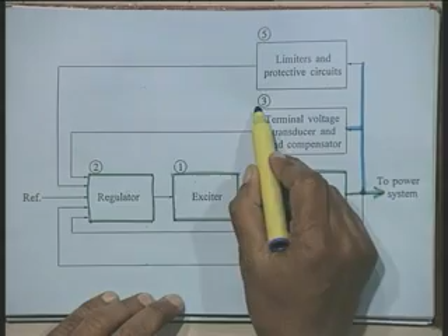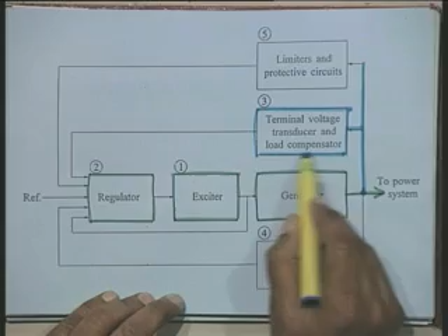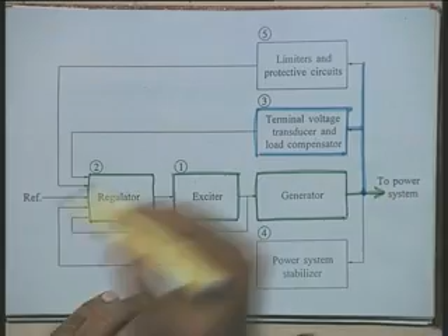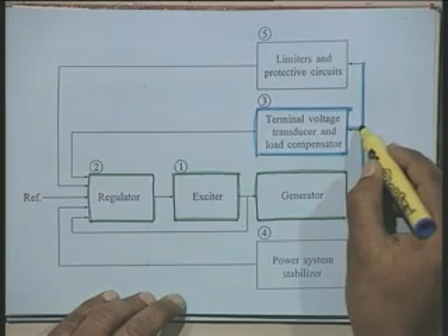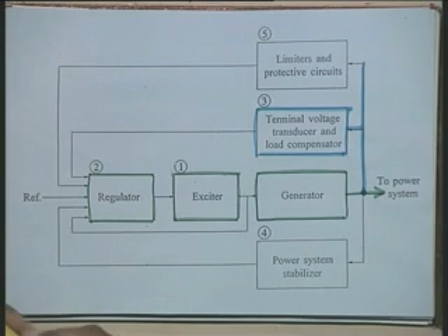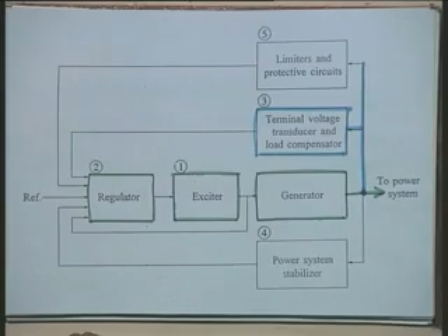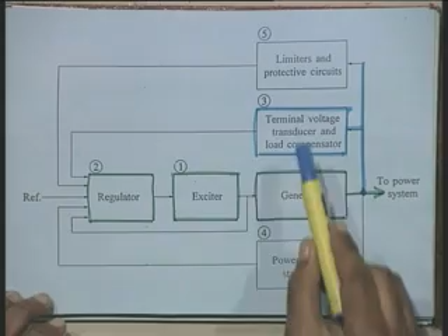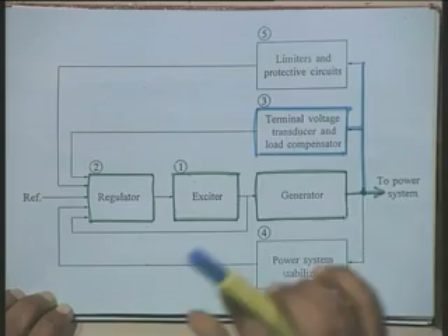Now, this is the block which shows the terminal voltage transducer and load compensator. I shall separately talk about the load compensator, but you can understand that when I want to regulate the terminal voltage of the synchronous generator, we sense the terminal voltage. Since the terminal voltage is AC, it may be 11 kV, maybe 16 kV depending upon the design of the machine, therefore, at this point the voltage is stepped down, okay, and then it is rectified and we get a DC signal which represents the terminal voltage of the synchronous generator. That is why the terminal voltage transducer is used, that is, you step down the voltage, you rectify and bring it down to a level which can be used for the purpose of control.